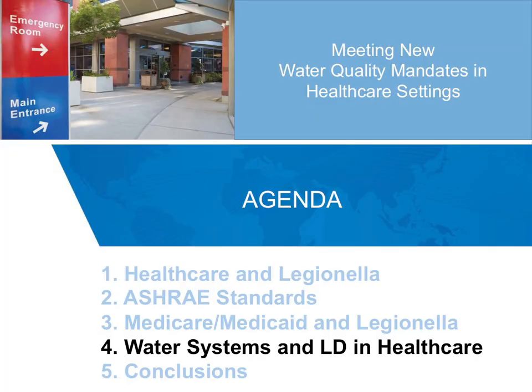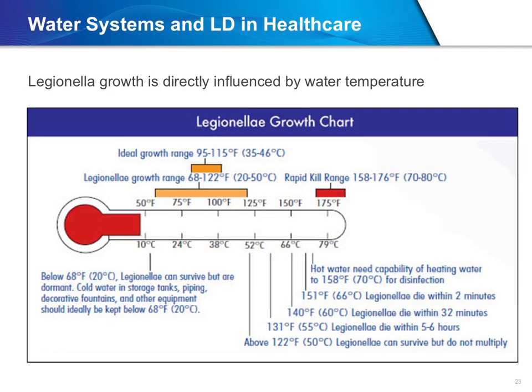We have covered the nature of the health issue with Legionella, the 7-part process of the ASHRAE Standards, and the federal agencies that are making water management for reduction of Legionella a requirement for funding. Let's now turn our attention to the specific parts of a water system in healthcare facilities that need to be addressed. The first overriding issue in looking at water systems and Legionella is the direct relationship between bacteria growth and water temperature.